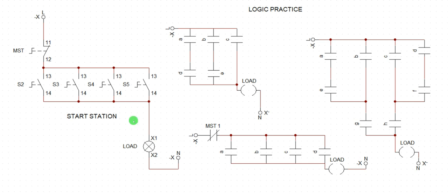Okay, but when it comes up and there is a necessity to shut down that operation, and you are not around, and nobody can access where this switch is located in your own apartment, you will now come to this master switch and shut it down. The master switch must be installed where it is accessible to the whole of these people. So this one should be installed close to the pump location, while the rest of the switches will be installed right inside individual flats. So I've given you three applications where this can be useful.